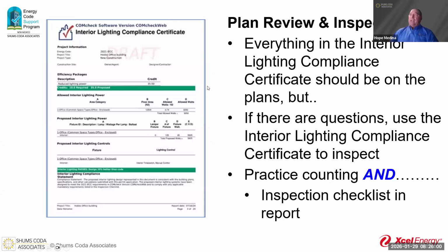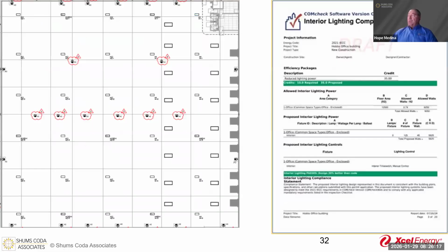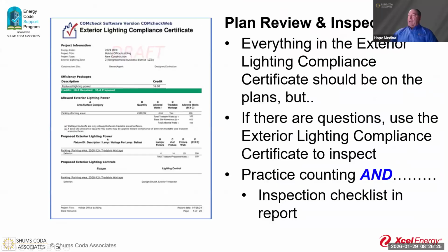Our interior lighting compliance certificate. With this, it tells us what we have happening as far as number of fixtures, watts per fixture. Does it pass? Does it not pass? We need to make sure we have this as well as our inspection checklist. And one of the great things about these certificates is learning to count.